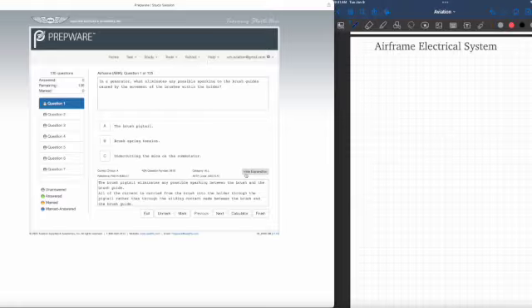So in a generator, what eliminates any possible sparking to the brush guides caused by the movement of the brushes within the holder? The brush pigtail. The brush pigtail eliminates any possible sparking between the brush and the brush guide. All the current is carried from the brush into the holder through the pigtail rather than through the sliding contact made between the brush and the brush guide.